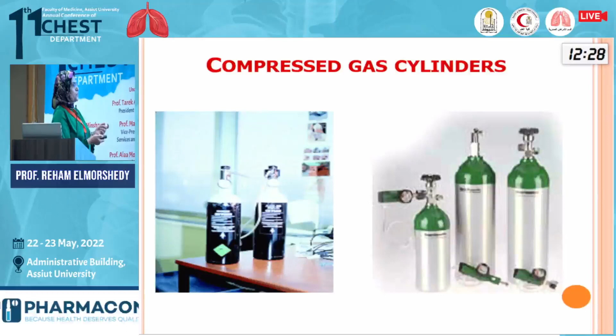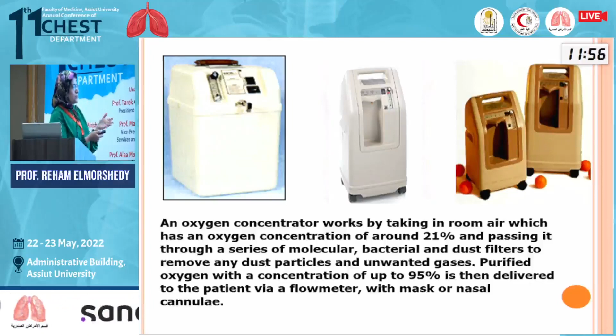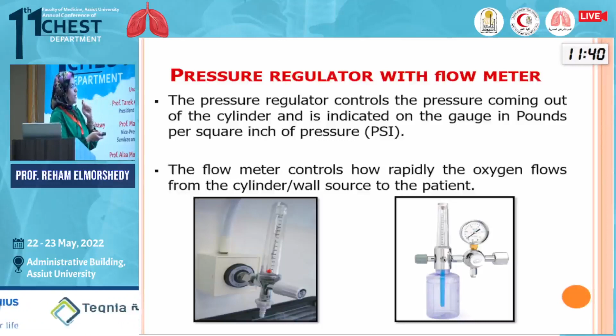This is the oxygen concentrator. This device takes the room air oxygen concentration of about 21% and passes it through many filters to remove any unwanted harmful gases, bacteria or viruses, and it gives the patient an oxygen concentration up to 95% via a flow meter with a mask or nasal cannula. This is the pressure regulator with a flow meter, which is found in hospitals. The pressure regulator controls the pressure coming out of the cylinder or the wall source and is indicated on the gauge in pounds per square inch. And the flow meter controls how rapidly the oxygen flows from the cylinder or the wall source to the patient.